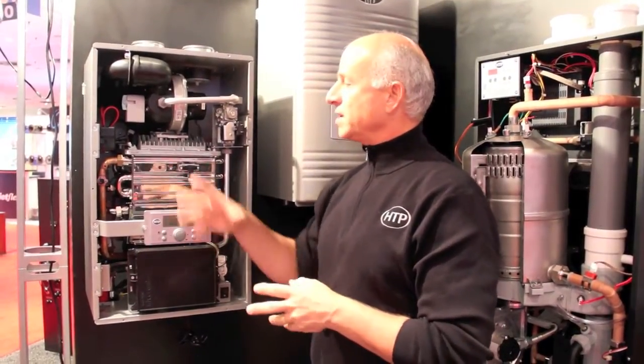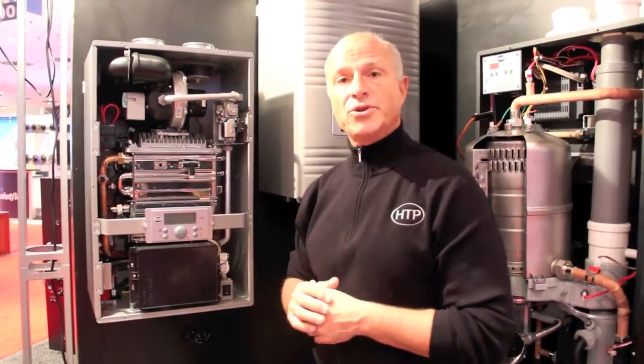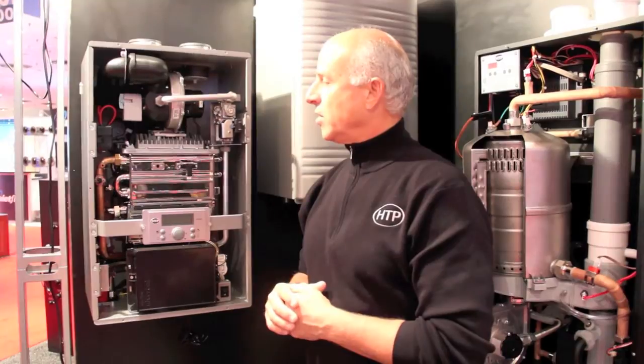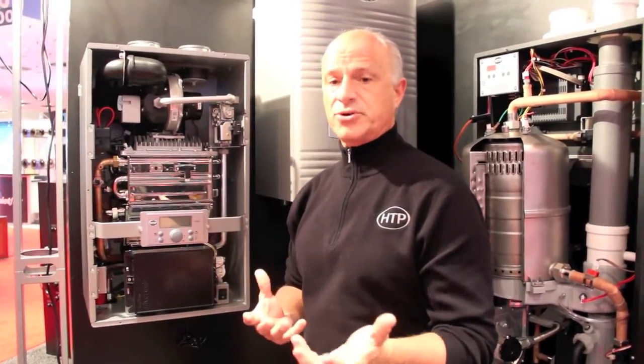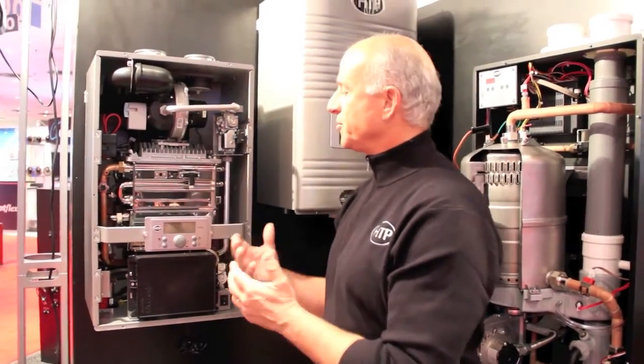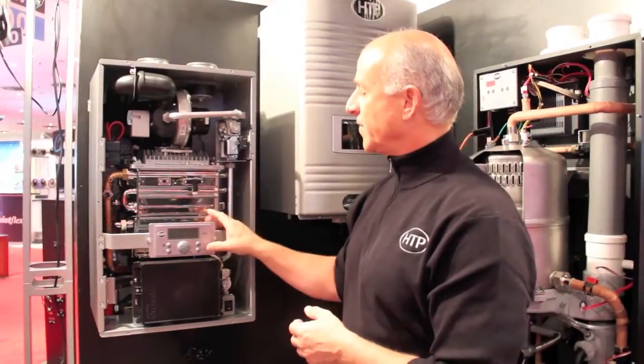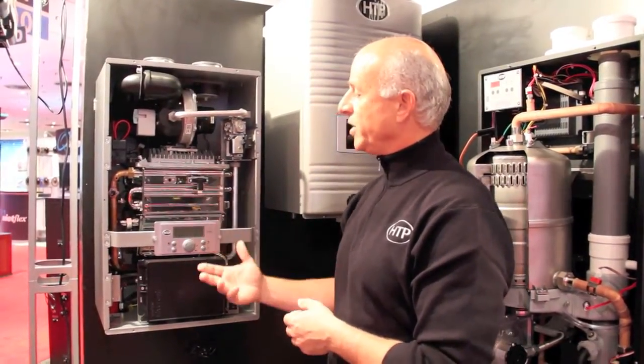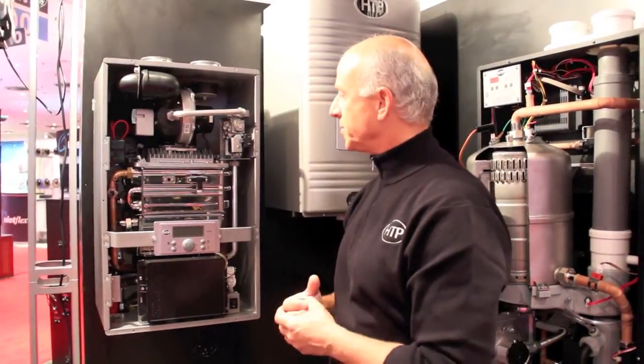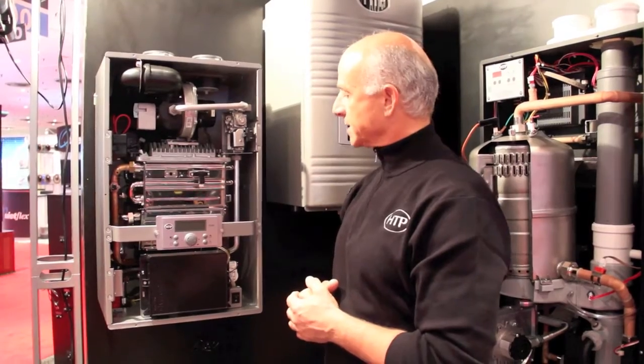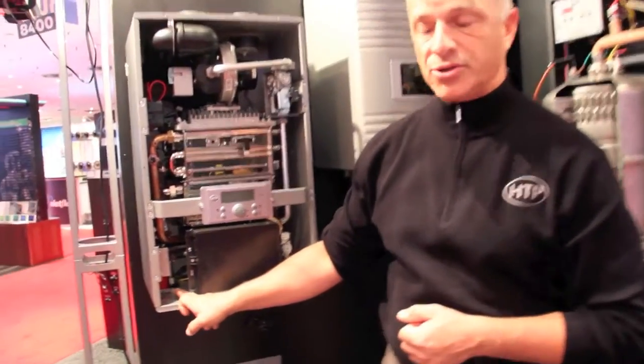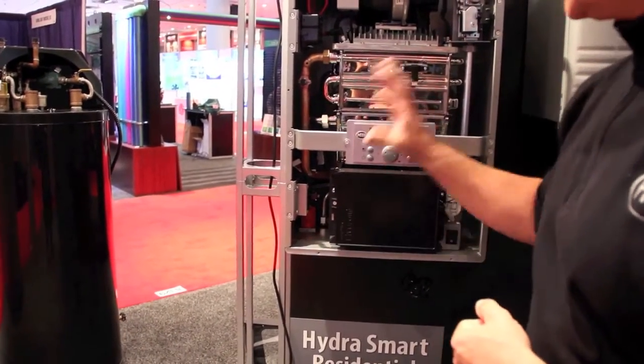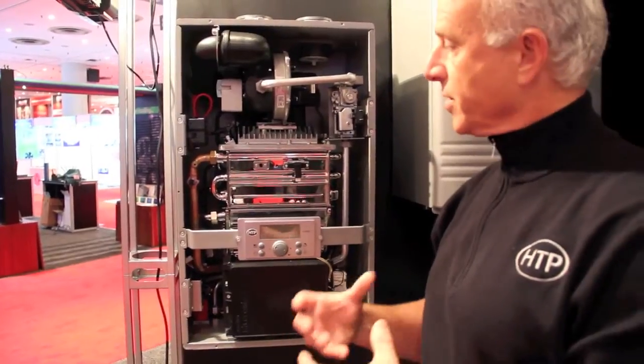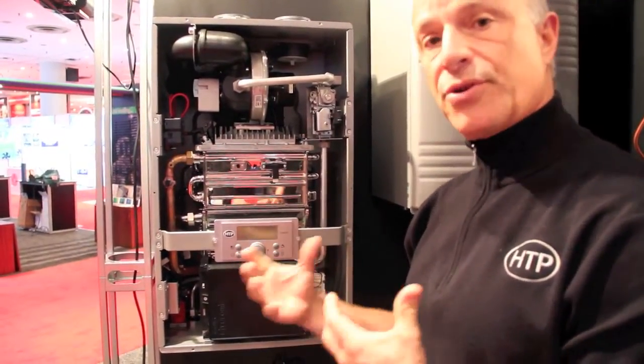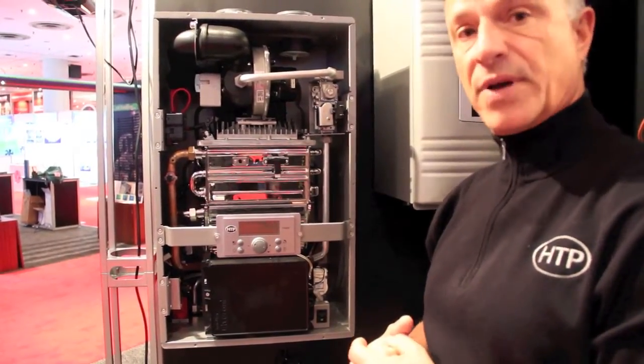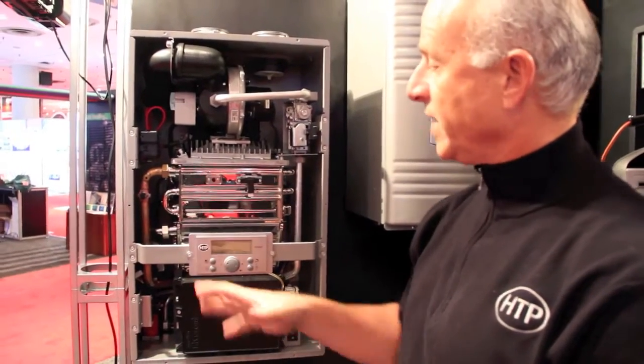It's a very, very robust design. The tube diameters are a lot larger than what you normally see in the marketplace today. So it gives you more volume, better flow characteristics, less pressure drop, which is a nice feature. There's some other features. The display panel is very easy to operate as far as just to set water temperature and to see what the system's doing. You can monitor flow, you can monitor your return and supply temperature as the unit's operating. It's got a seismic sensor, a little red device back here. The seismic sensor will shut the unit down if there is an earthquake or large amounts of vibration, which is a nice feature in those areas that require some type of seismic bracing. So that's a very unique feature to our unit.